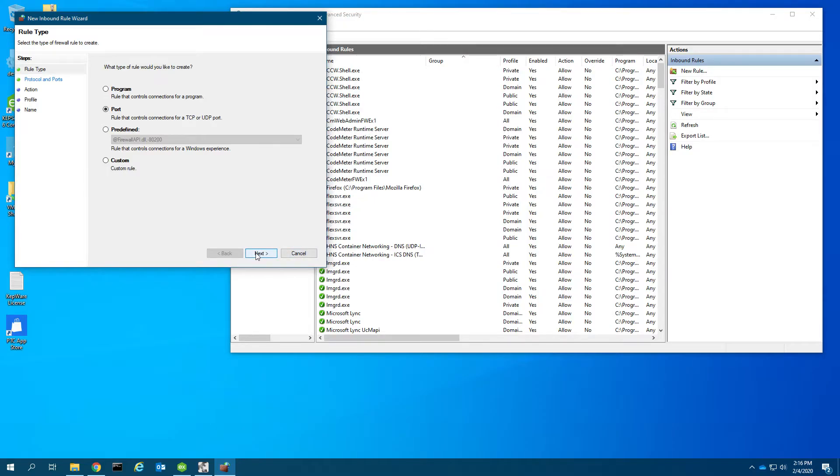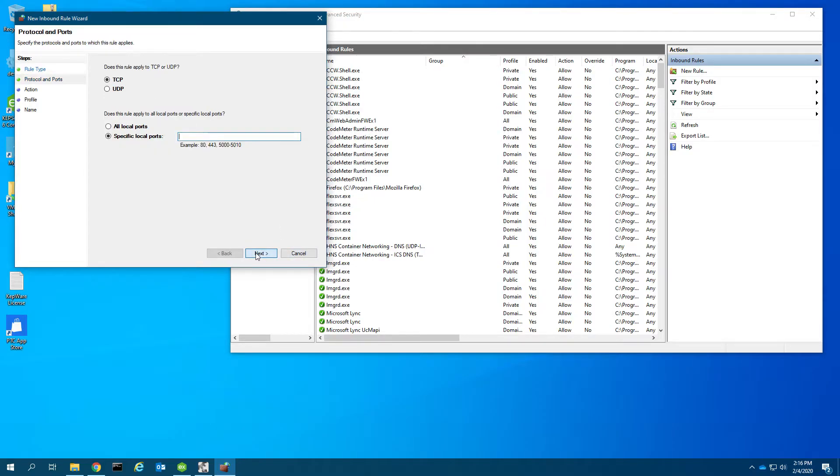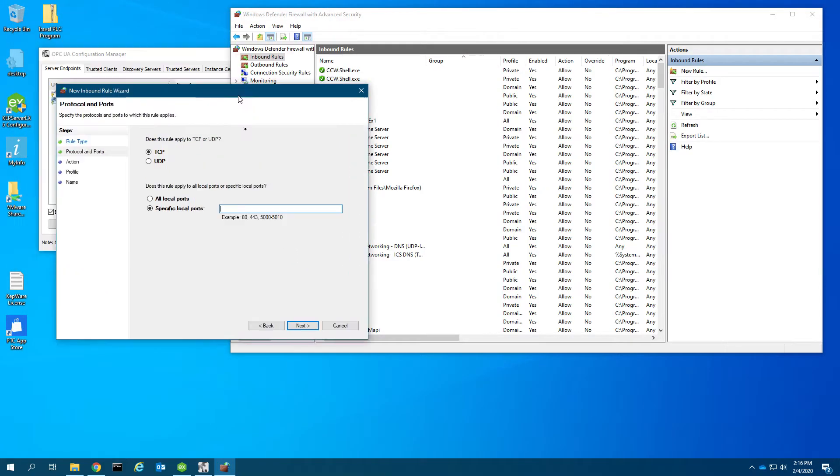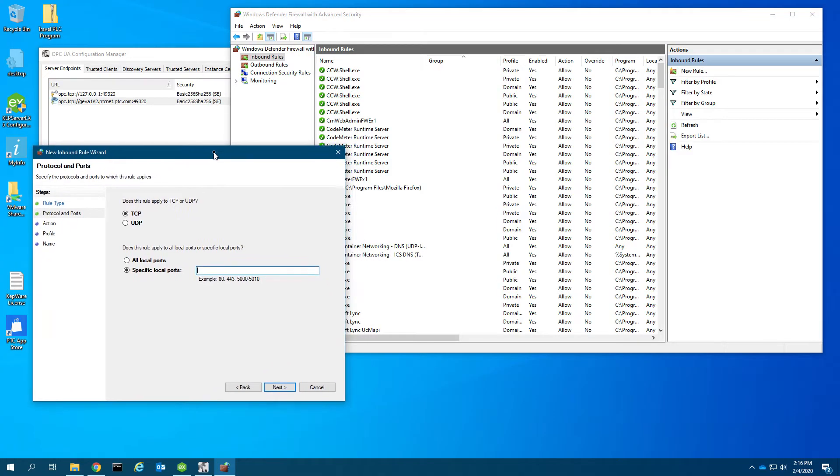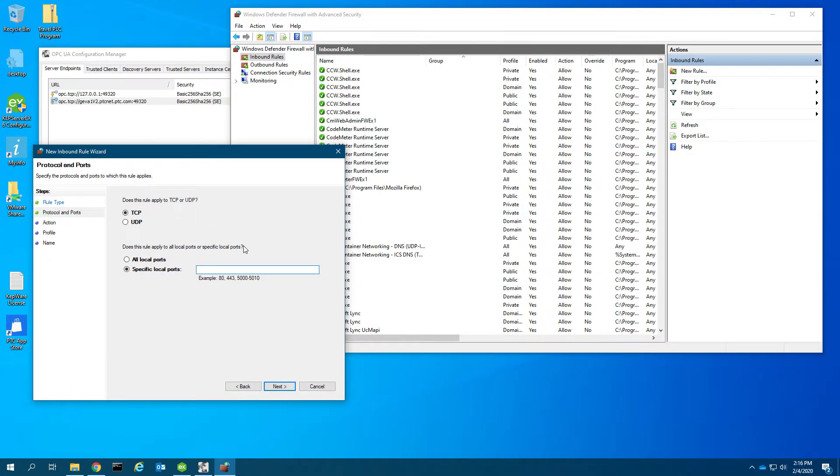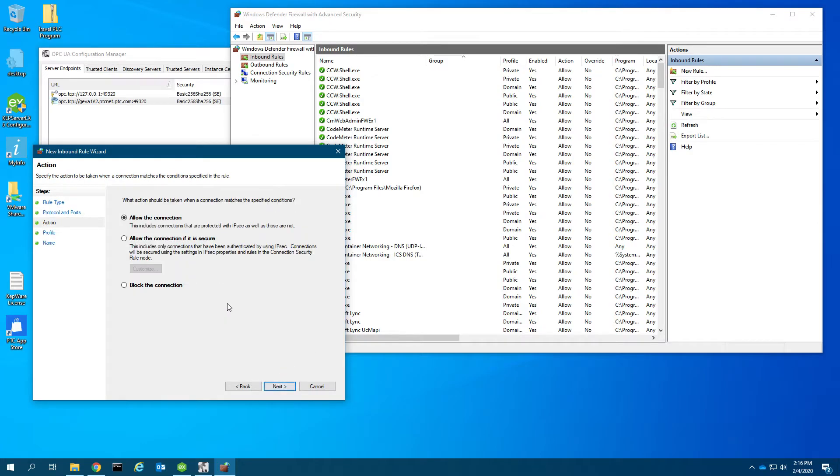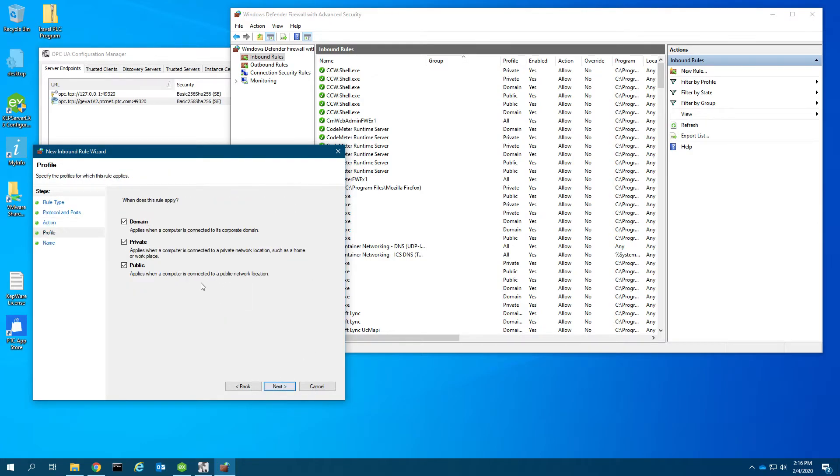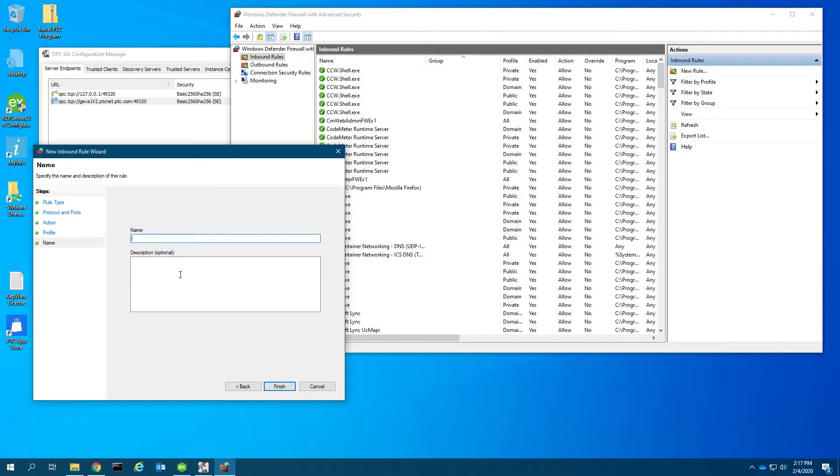I'm going to do a port-based rule. We're going to say OPC UA 49320 on TCP. Allow the connection, not on internet-facing interfaces but just on private and domain network interfaces. Give it a name: OPC UA server interface.